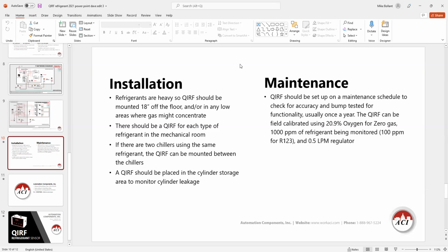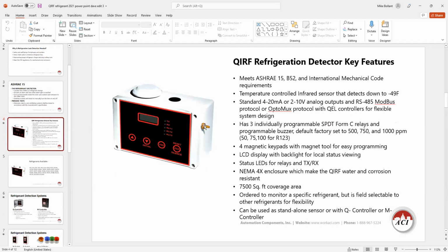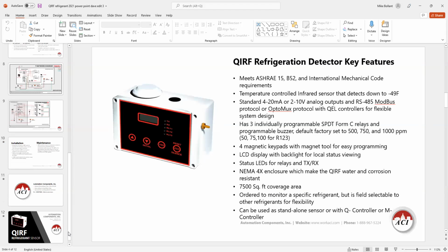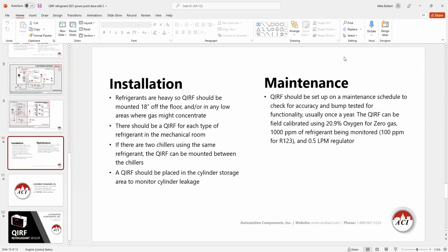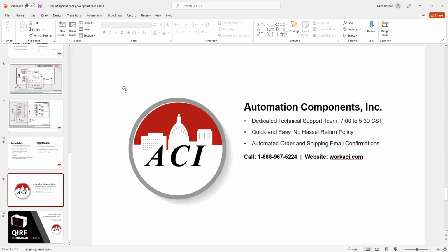Maintenance: the annual bump test, or whatever your customer wants, if it's six months, a year, whatever. But we do recommend that at least once a year you go out and do a quick bump test. And right on the side of the sensor, right here is your test port. And the QIRFs all come pre-programmed. They're pretty much all the same, with the same relays, set points, and spans on the Freon as well. In a nutshell, that's pretty much it.